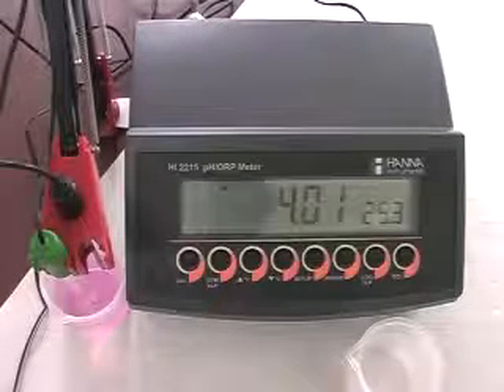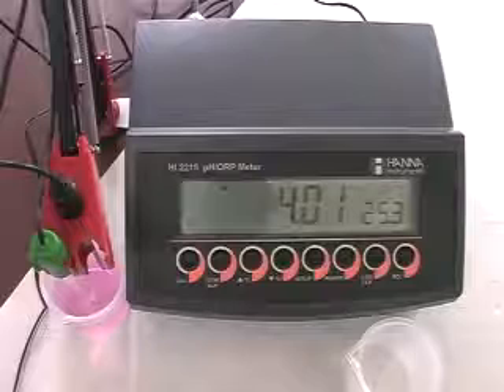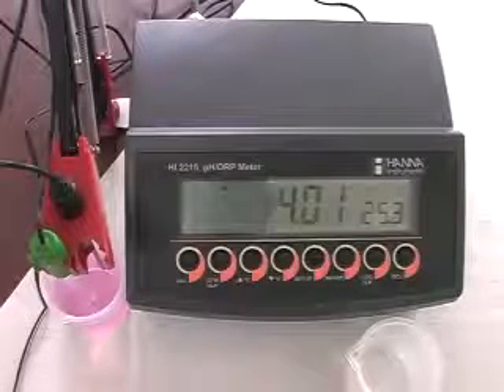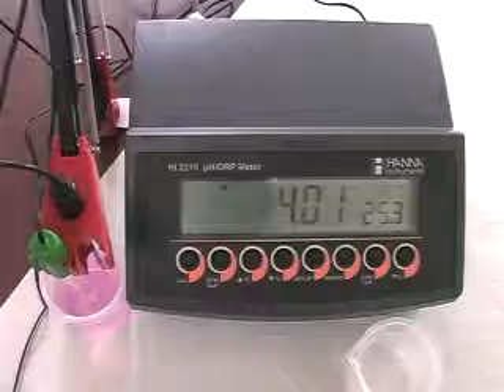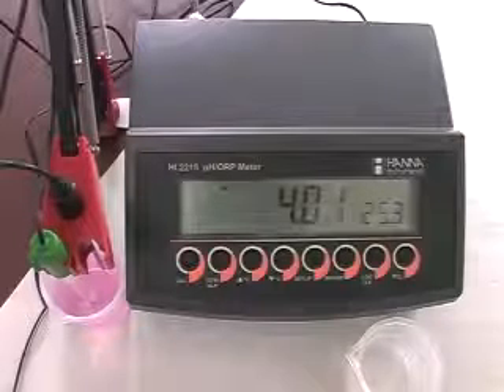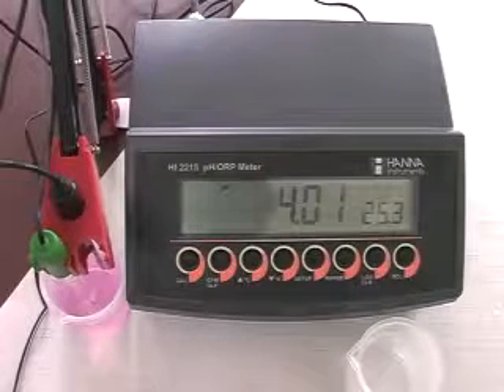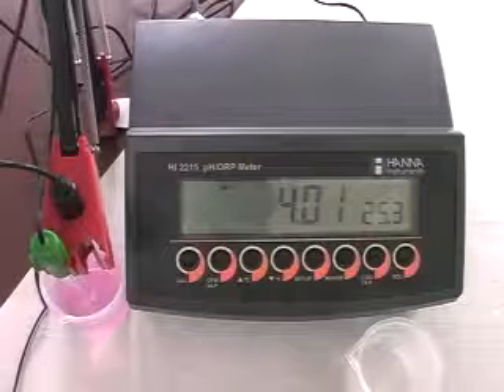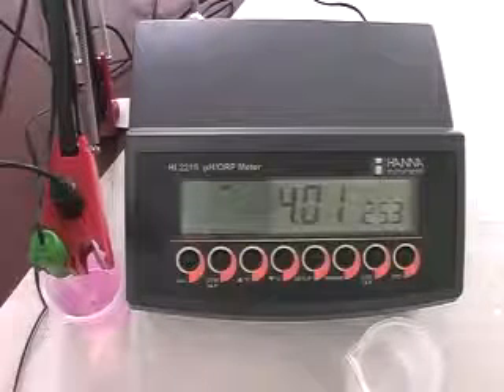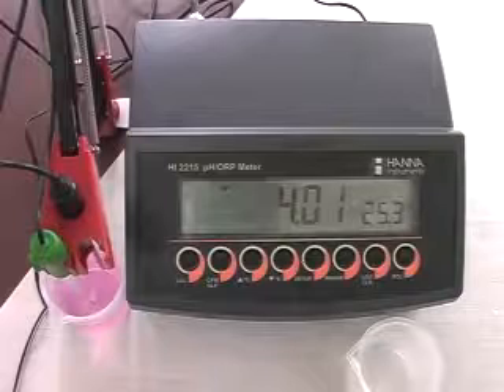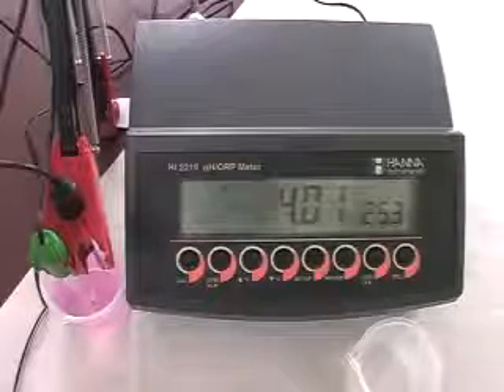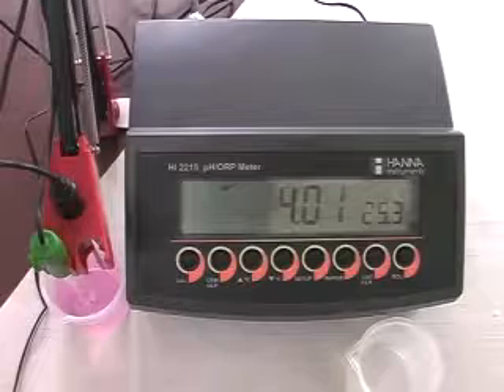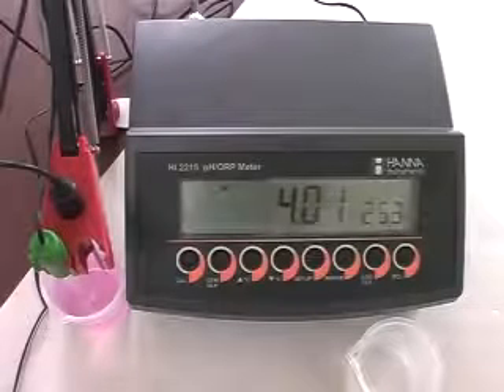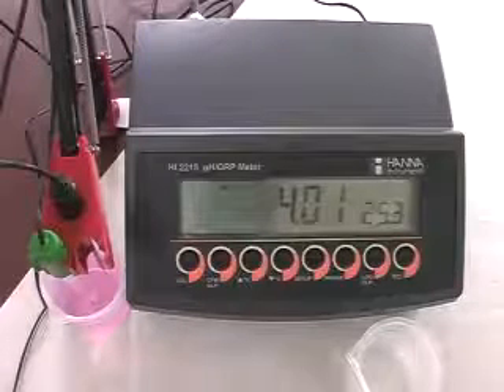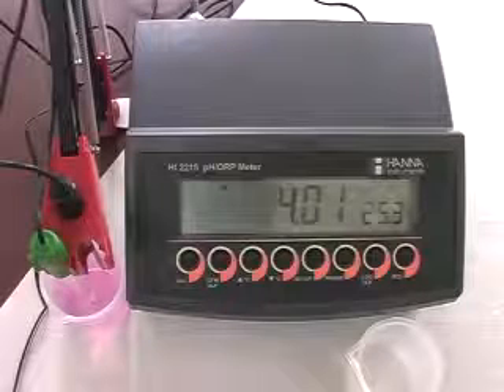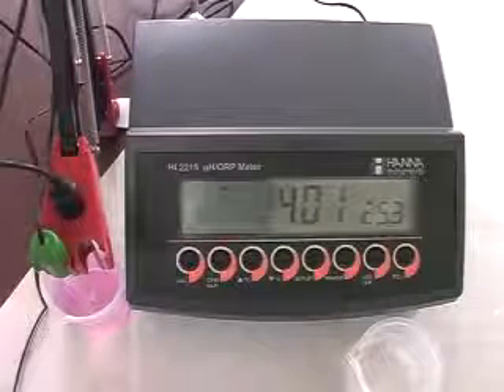This is KS Metkari and I am going to show you how to calibrate our bench pH meter model number HI2215. Basically, HI2215 is a microprocessor bench pH meter which has a 5-point calibration facility. But today we will see how to calibrate your meter for pH 4 and 7.01 buffer solution. Basically this is a 2-point calibration, so I will show you how to perform 2-point calibration.